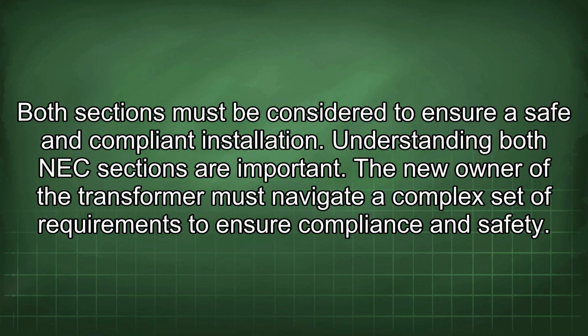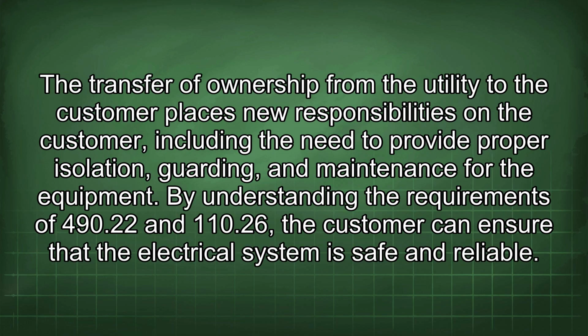The new owner of the transformer must navigate a complex set of requirements to ensure compliance and safety. The transfer of ownership from the utility to the customer places new responsibilities on the customer, including the need to provide proper isolation, guarding, and maintenance for the equipment. By understanding the requirements of 490.22 and 110.26, the customer can ensure that the electrical system is safe and reliable.